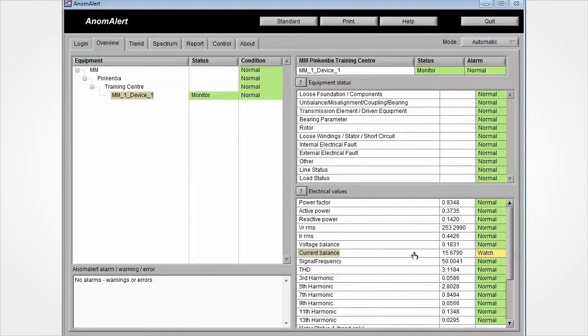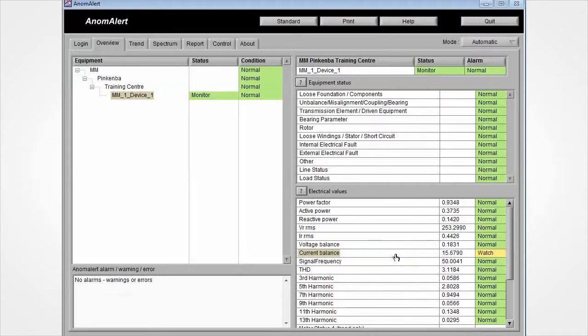Every 90 seconds, Anomalert calculates the parameters of the connected motor or generator and compares these values to its learnt model values.